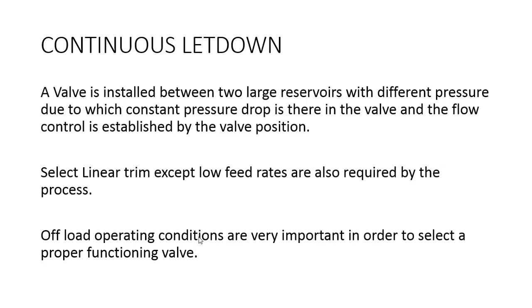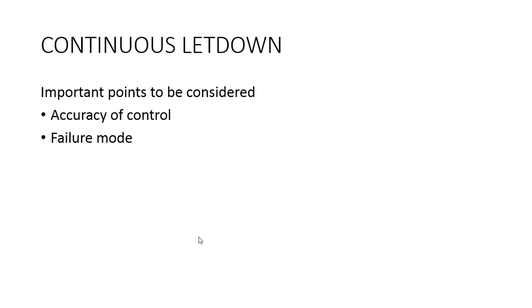Next, the important points that we need to consider for continuous letdown valves are accuracy of control and failure mode. What do we mean by accuracy? It is the most important function. It has to maintain a constant pressure, flow or temperature, which is essential to process product quality. A continuous waving output may cause short and long term damage to the equipment. Second, the failure mode: normally fail last is considered, so the system is not disturbed. However, the engineer may prefer a fail close condition, so the operator is alarmed regarding the valve failure.